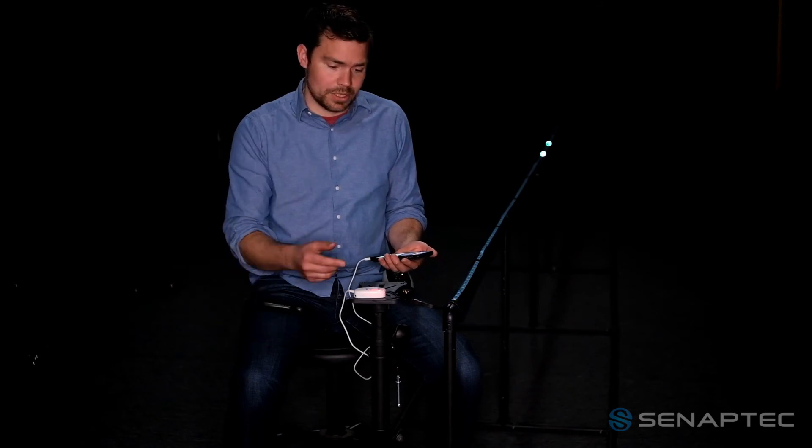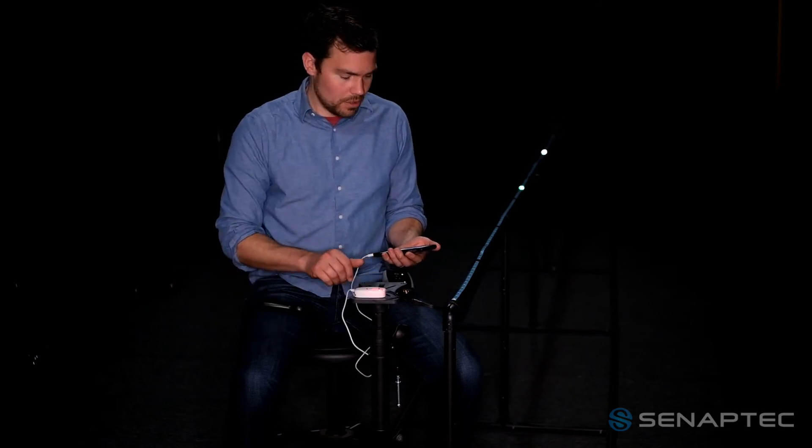A Synchrony device can be triggered in multiple ways. You can use the button on the main device, use your phone to trigger, or plug in external triggers such as hand triggers or foot triggers. Senaptec also provides a proximity sensor you can trigger based on sound, motion, or breaking a light beam.